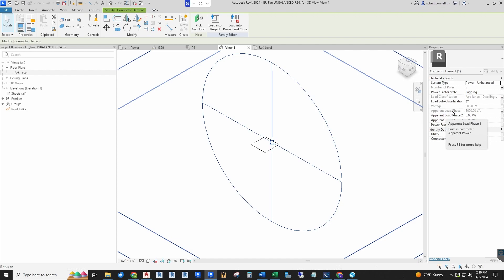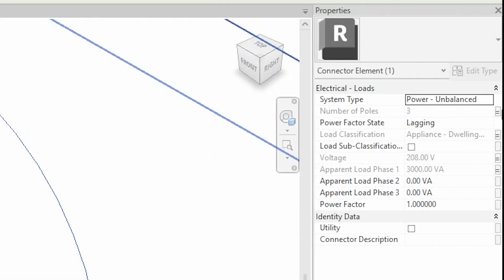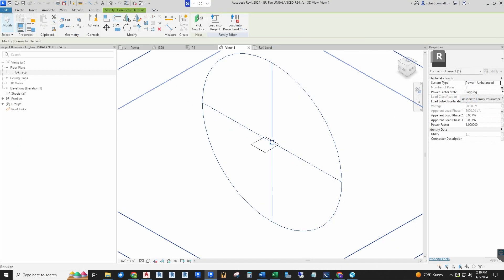Click on the electrical connector and go over here and look at what's going on. Down here we have a apparent load for phase 1, phase 2, phase 3, because we have it set up as three poles. Now these are grayed out because if you look at the far right, a tiny little equal sign—this is the way that you can associate this parameter within the electrical connection. You can associate it with a family parameter so that you can get to it in your model.